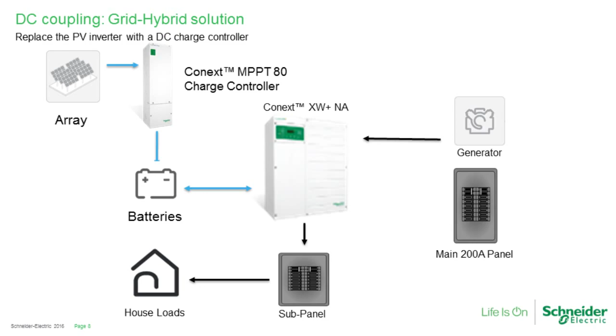If the sun just isn't shining and the loads are large enough, this really does make for a very versatile solution, and also can help keep the cost of storage down, because the generator can actually act as that charging source again and provide that backup power above and beyond just what the batteries can provide. So sometimes if the loads are very large, it financially can make sense to bring a generator in instead of just doing batteries and providing a very, very large source of storage in the form of lead or advanced storage. So we will again touch on this a little bit more because there are some benefits and detractors to this idea, and we'll continue on that path.